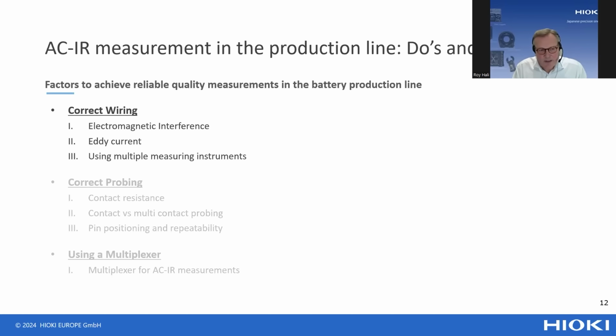The first thing we are going to look at is correct wiring. Poor test results are basically related to three main categories: the wiring between the battery and the battery tester, electromagnetic interference due to the use of motor inverter drives in the production line, and the effect of eddy currents and the use of multiple testers at the same location, which can also influence the accuracy of the measurement.